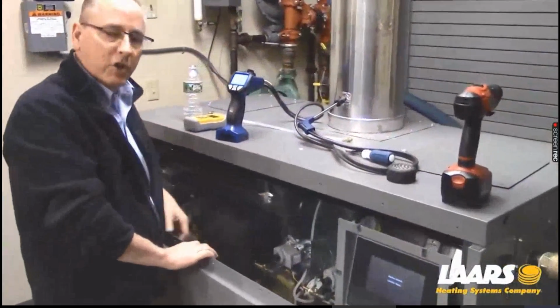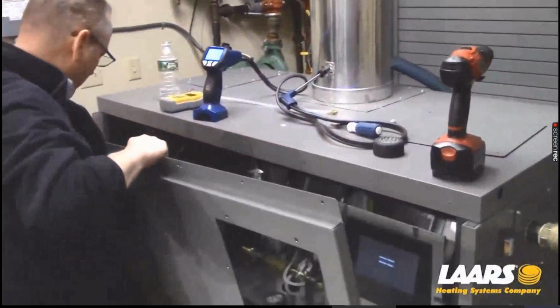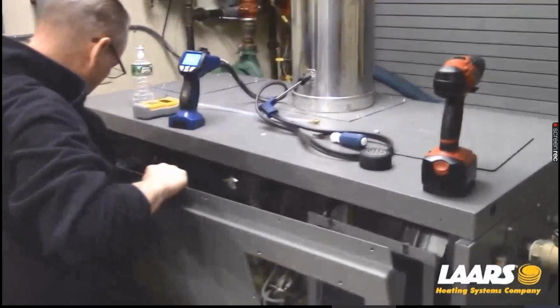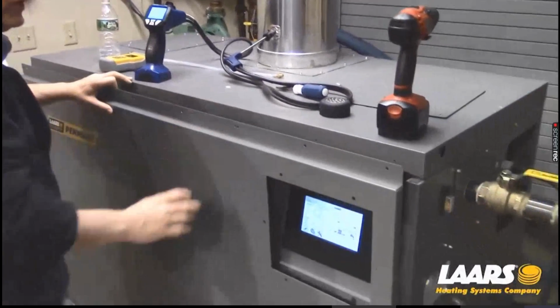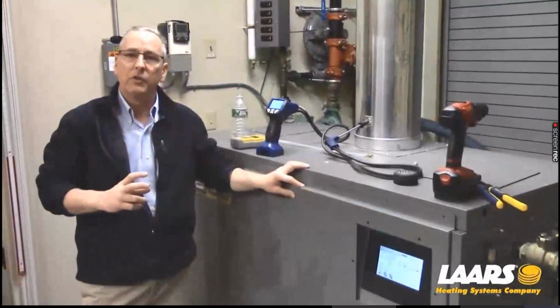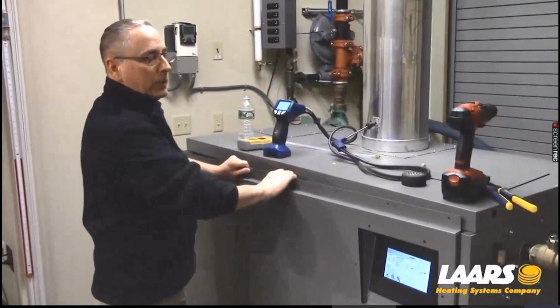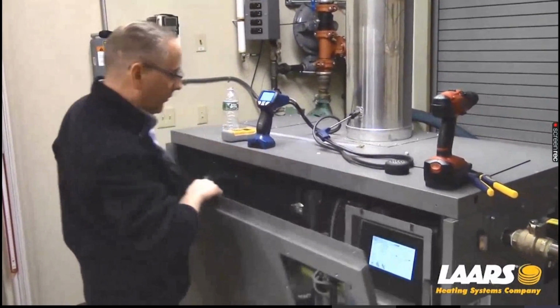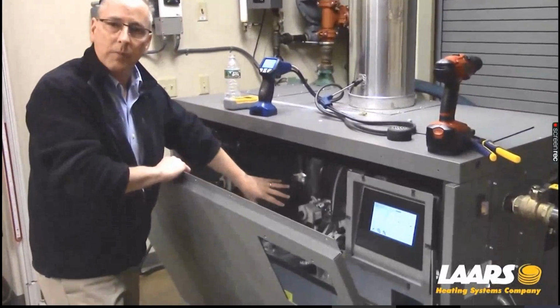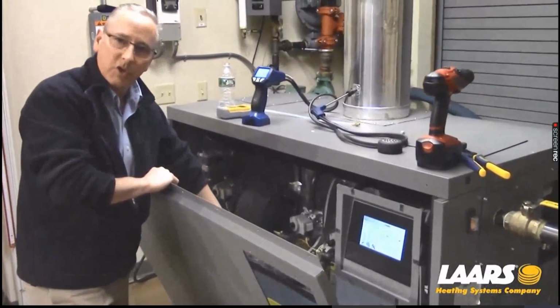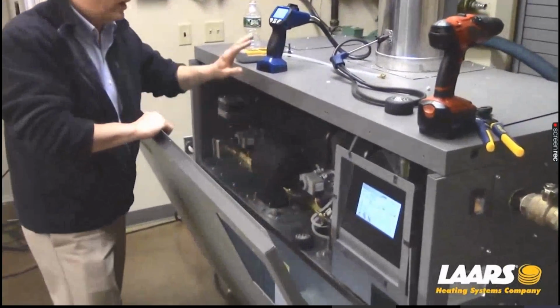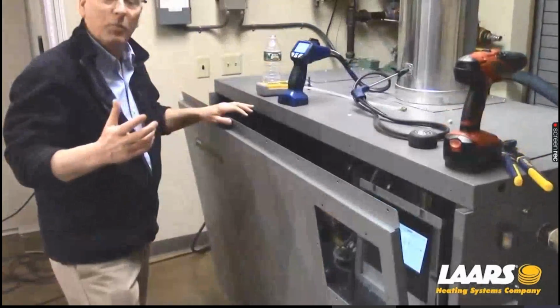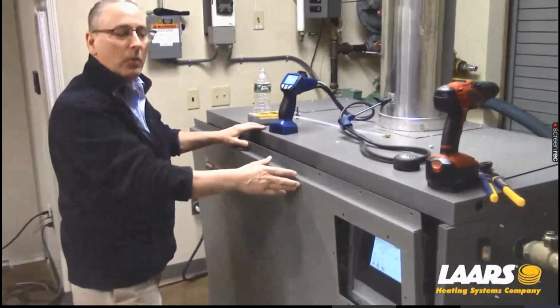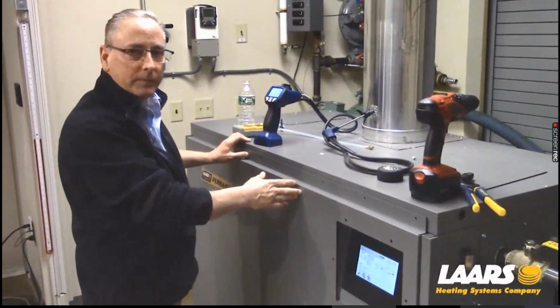Now when you're making an air shutter adjustment, put the cover back on if you're ducted outside the building. If you've got a 6-inch vent collar or 7-inch vent collar, you want to be able to restrict that air. You don't want free air coming right in here to the blower. So again, when you're making combustion adjustments on the air shutter with your analyzer, if you're bringing combustion air into the boiler, put the cover back on.